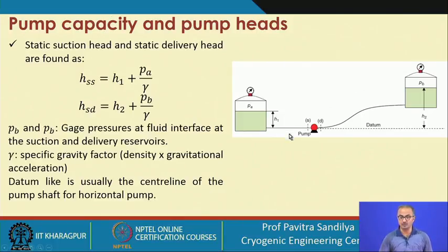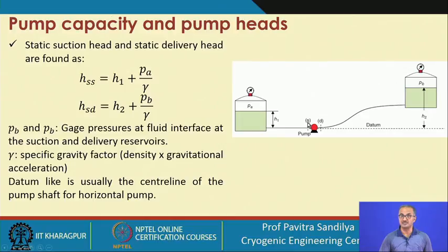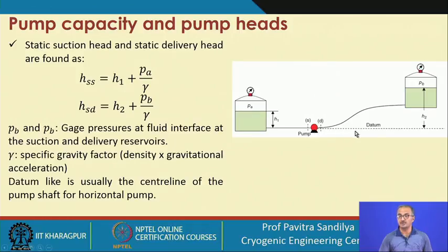In this particular figure we see how to find out the static suction and static delivery heads. We have two tanks, with pressure gauges fixed at both tanks to know the pressure inside. The pressure PA acts on the suction tank and PB on the delivery tank. S represents the suction side and D represents the delivery side of the pump. We take a datum, usually the centerline of the pump shaft for a horizontal pump, since all energies are expressed relative to this datum.